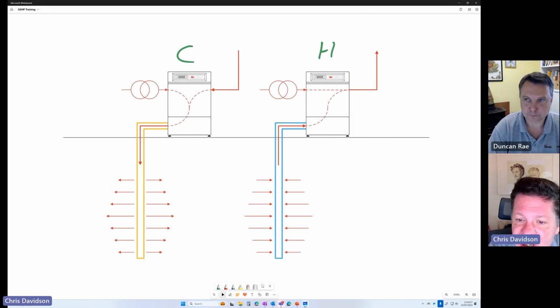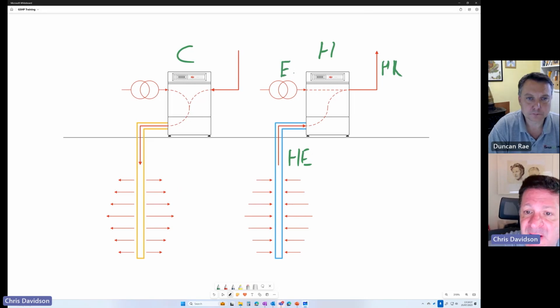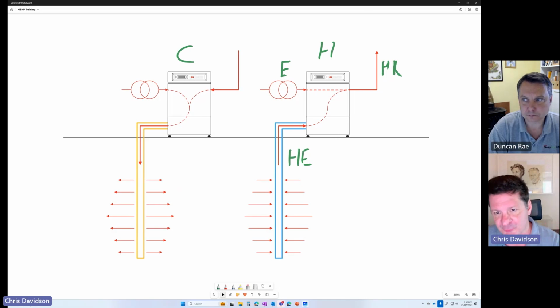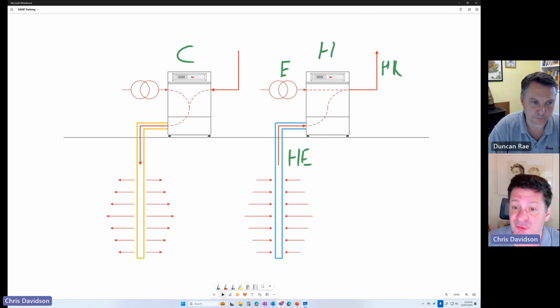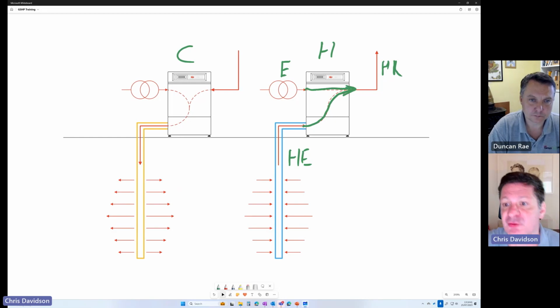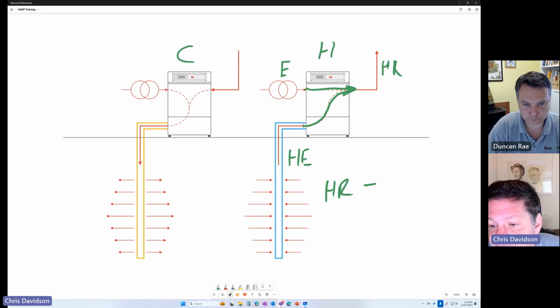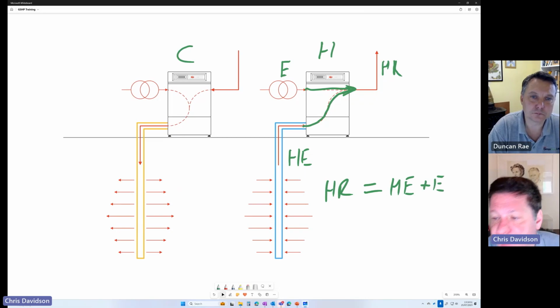So the heat being extracted from the ground is called the heat of extraction. And the heat being rejected into the building is called the heat of rejection. And there's a third part of energy involved, as I mentioned earlier on, which is the electrical energy consumed by the heat pump to make the thing work. Now, through the forces of friction, very, very close to 100% of that electrical energy ends up as heat also. So the heat coming from the ground is actually added to by the electrical energy being consumed by the heat pump. So our heat being rejected into the building is very, very close to equal to the heat being extracted from the ground plus the electrical energy.